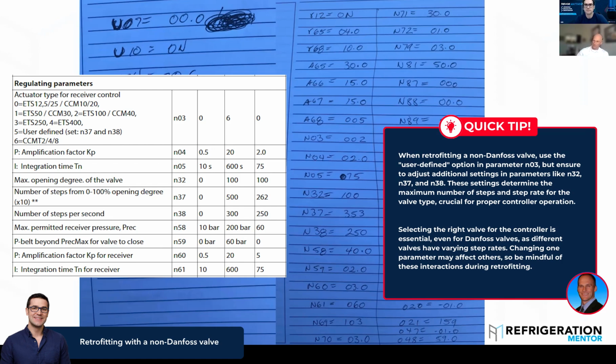But then you have to keep in mind, okay, we've told the EKC it's a user defined valve. We now need to go into other parameters. So there's N32, N37, N38. N37 and N38 specifically would be the additional settings that you now have to program that tell the controller what the maximum number of steps are and what the step rate should be for that type of valve.